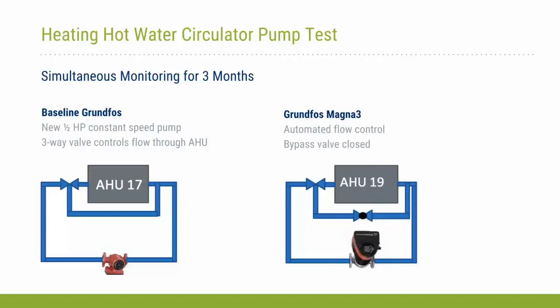There was a pretty big difference, though, in the approach. One of the things was the air handling unit 17 pump had failed prior to us starting the demo. And so we had to replace the baseline pump with a modern market standard pump by Grundfos, which ended up being a lot more efficient than an older 10 to 15 year pump that you would see in that application. And so this is more of an analysis of what does a new market standard pump look like versus a new high performance circulator pump. So for air handler number 19, we put in the high performance circulator pump, and then we also closed off the bypass valve on the 3-way valve there. That bypass valve essentially for constant volume systems allows the water to bypass the heating coil when the valve starts to close down. And so you need to close that for variable speed applications so that you're able to just directly modulate the flow that's going through those.